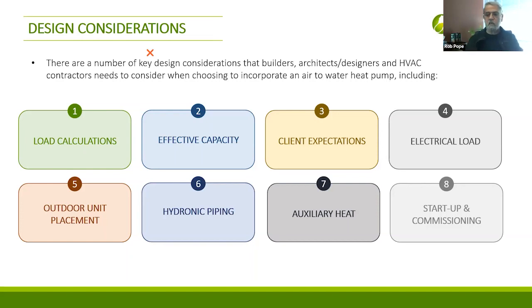Ultimately, one of the weakest links in our industry for HVAC systems in Part 9 buildings and residences is the commissioning. Any piece of equipment starts off in a factory, who knows where, anywhere in the world - it doesn't know where it's going to live. It shows up in a box with factory default settings and potentially issues. There might be component failures, something might have happened on the way there, or during installation. Either way, it doesn't matter what - just before you're ready to hand over that house and system to the homeowner, it is critical to put the system through all its phases.